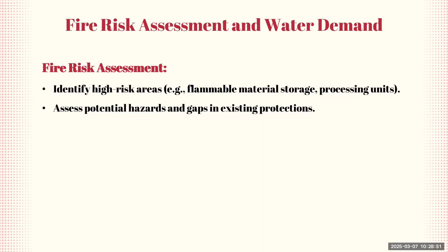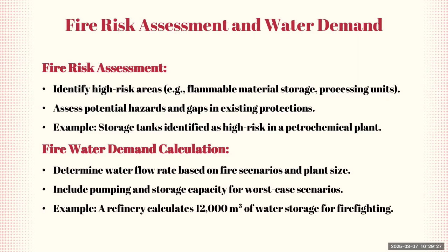Okay, and then for the fire water demand calculation, we need to determine the water flow rate based on the fire scenarios and the plant size. So how much water will be required in our case? This will include the pumping and storage capacity for the worst case scenario. We need to ensure that we have a backup storage where, if the fire goes on for a certain amount of time, our water will be able to sustain this extinguishing period. For example, a refinery will calculate around 12,000 cubic meters of water storage for firefighting. But of course, this depends on your plant size.